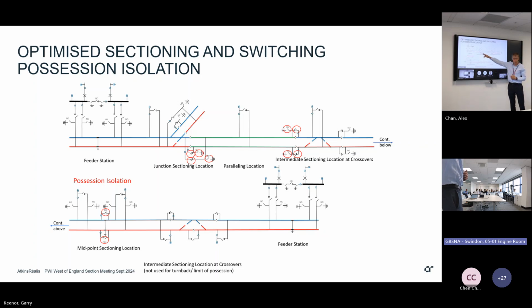Here we've also got earth switches so we can earth out - these are the circuit main earths, CMEs, that we've seen. If we adopt the principle that you only need intermediate earths around your work site, as long as your limits are secured, you can apply local earths rather than earthing up every 400 meters throughout your possession. You just put intermediate earths around your work site, and the circuit main earths prevent re-energization. With a two-track railway you don't have induction issues from parallel routes, but your local earths primarily protect against induction in the overhead line. Your isolation is secured through the CMEs, meeting electricity at work regulations, so as long as they're secured there's no way of energizing this - the intermediate earths just protect the workforce against induction, not re-energization. That's what these earths at the end are for.